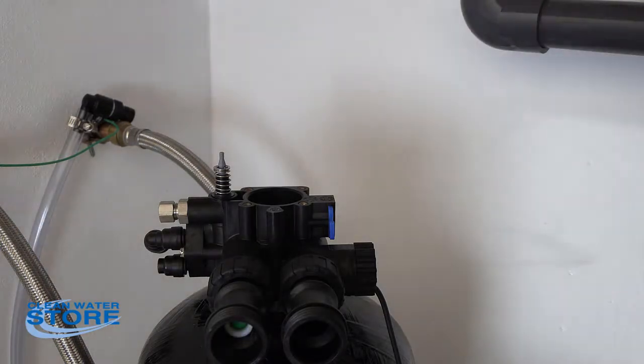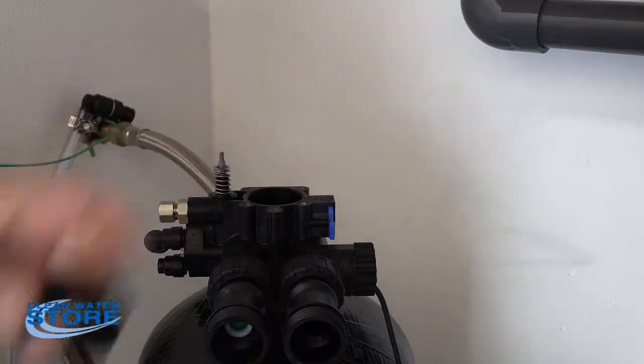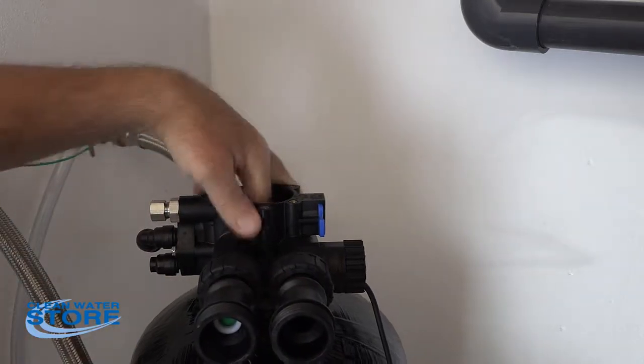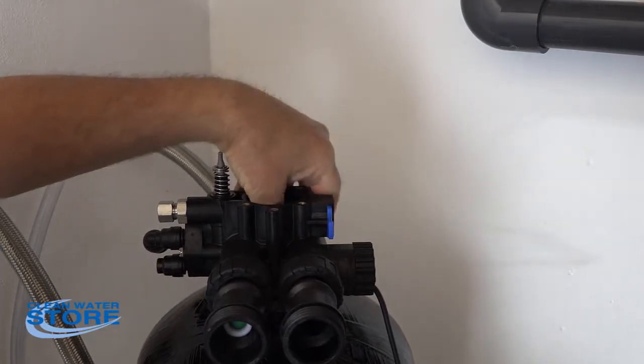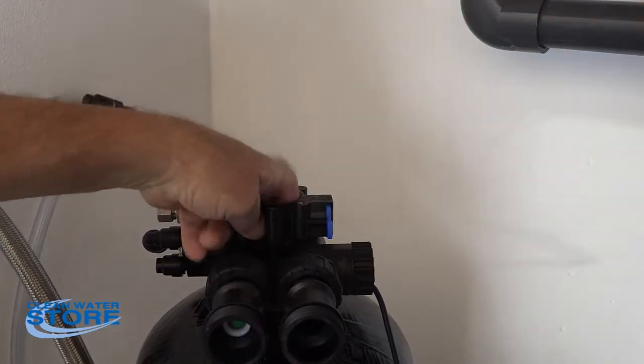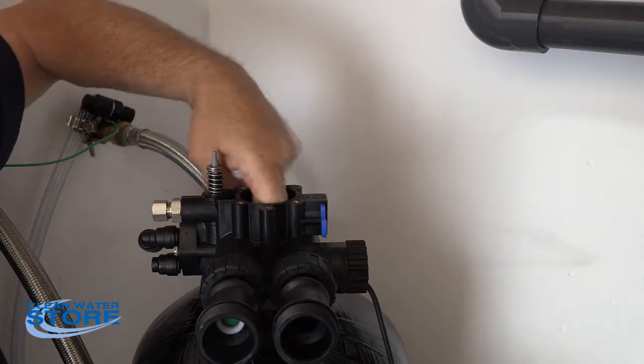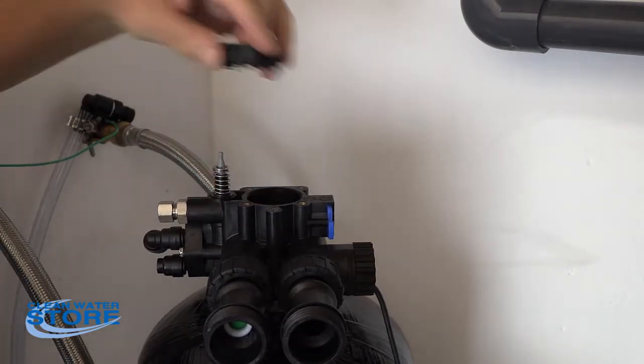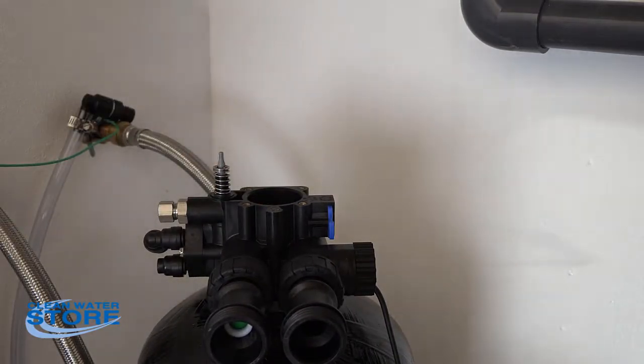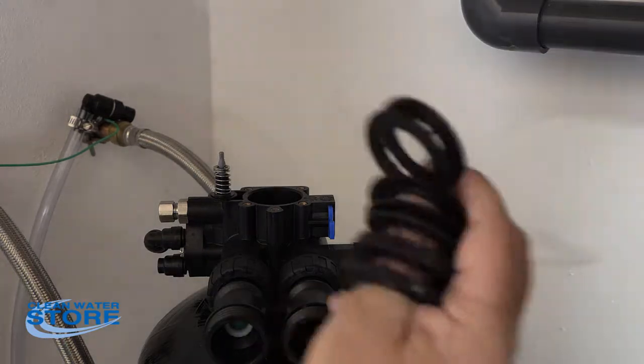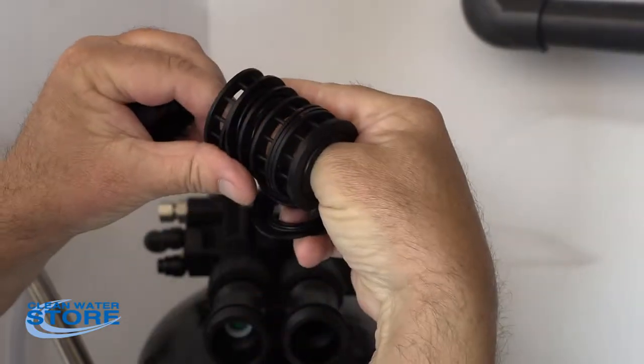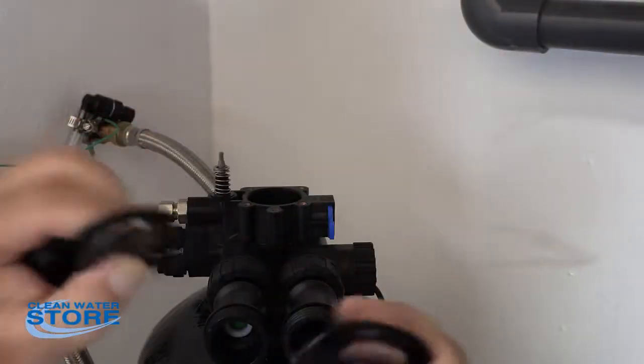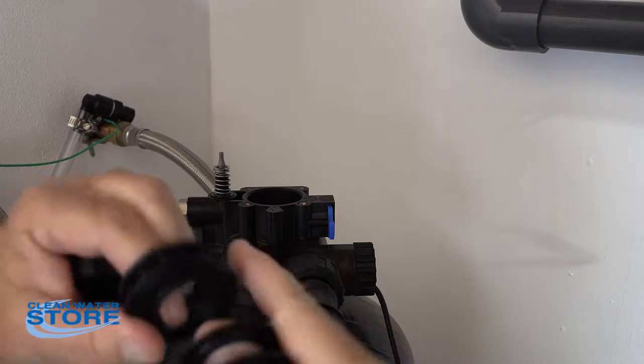For your piston, just clean it up real well and inspect it. For this part, what you're going to want to do is pull all the seals and spacers out. There are four spacers and five seals. There's one spacer at the bottom, the bottom spacer, that is different than all the other spacers. The spacers you got in your kit are flat and basically the seals go in between each one of them. So you go spacer, seal, spacer, seal.